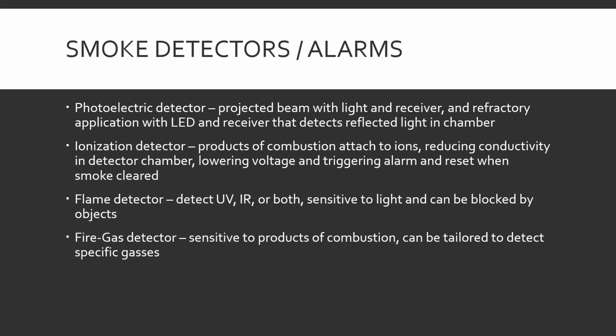And fire gas detectors. These are sensitive to products of combustion and can be tailored to detect specific gases. So these are used in places like foundries or welding shops, places where you can't use a flame detector because there's molten metal and bright sparks and all that stuff going around. That will cause the flame detectors to go off. You can't really use ionization because you're welding, there's smoke, there's spatter, what have you. Same with foundries, haze in the air, that'll set those off. And with photoelectric, maybe, but there's dust, who knows, machinery moving around could block the light or interfere with it.